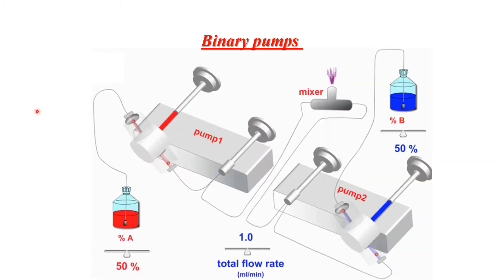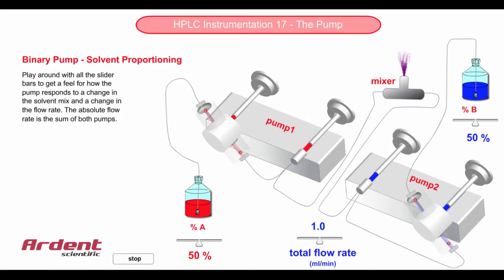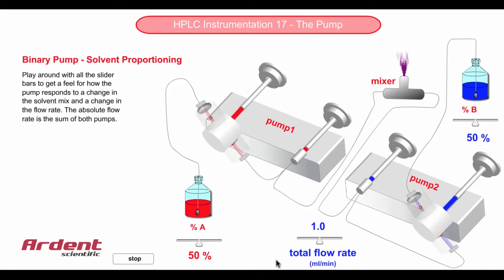This is a complete design of the binary pump, where we can notice a dual piston pump for solvent A and another dual piston pump for solvent B. The flow rate of each pump will control the ratio of the two solvents. To understand how the binary pump controls this ratio, let's look at some examples.